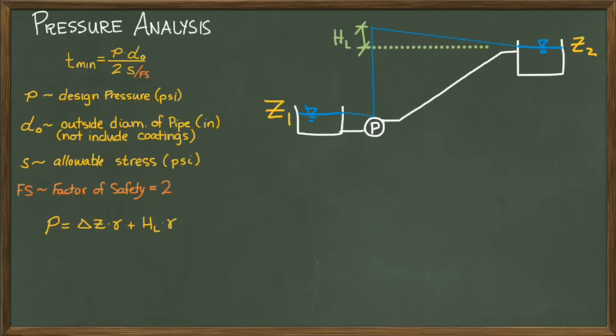However, even this calculation is not good enough because it does not account for the surge pressure. Surge pressure is a transient or non-steady condition that can be caused by a number of factors. The most common are when the pump turns on, when the pump shuts off, or when a valve closes in the system.